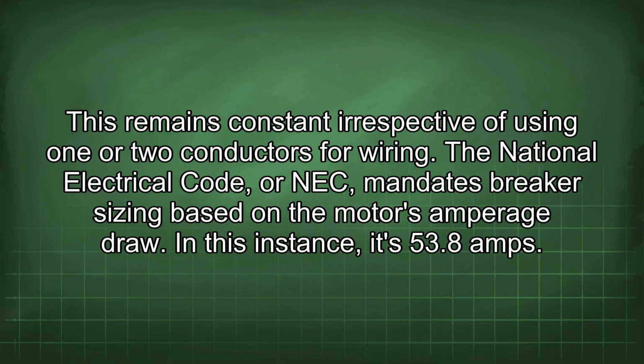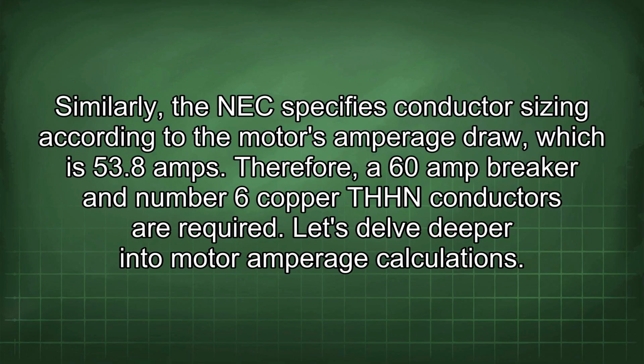The National Electrical Code, or NEC, mandates breaker sizing based on the motor's amperage draw. In this instance, it's 53.8 amps. Similarly, the NEC specifies conductor sizing according to the motor's amperage draw, which is 53.8 amps. Therefore, a 60 amp breaker and number 6 copper THHN conductors are required.